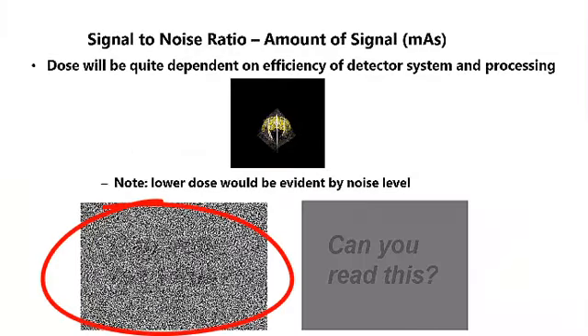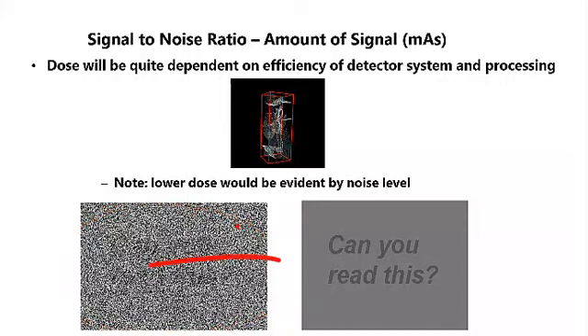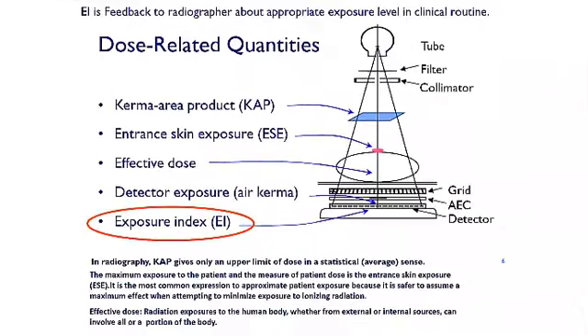If we don't have enough mAs, the lower dose gives us a noisy image. Noisy images, or quantum mottle, are caused by the lack of signal, and as we increase signal, we decrease the noise and we can read the image because we have enough data or information recorded.